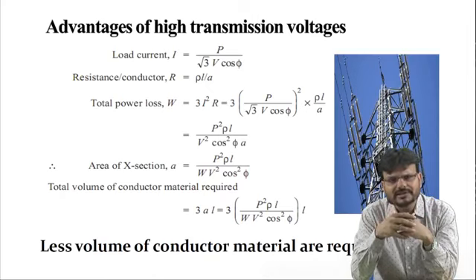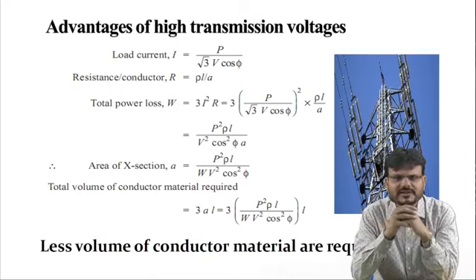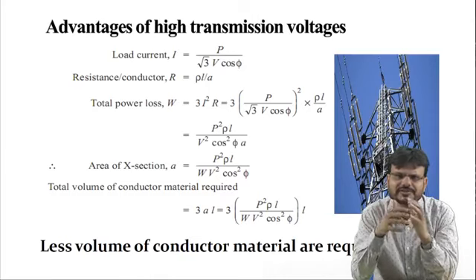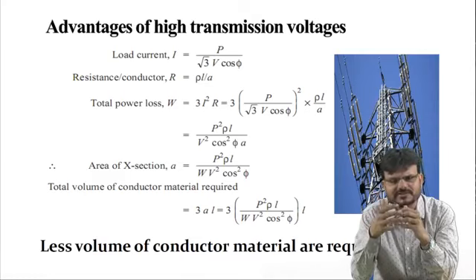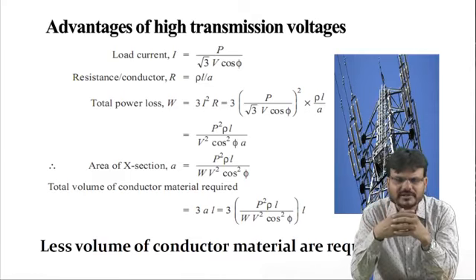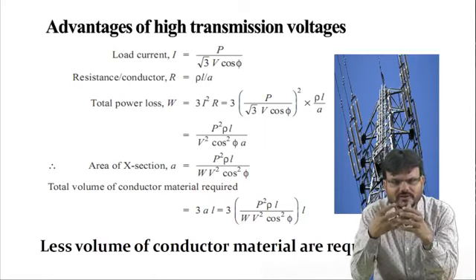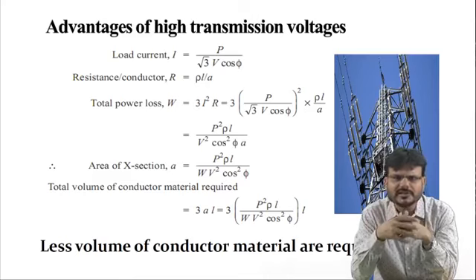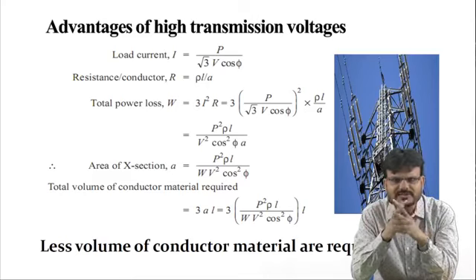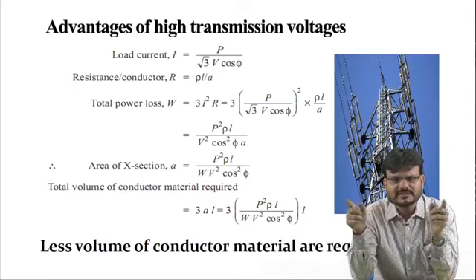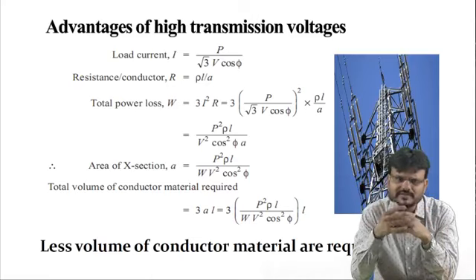So the total power loss W can be written as 3I square R. Just put the value I equal to P upon root 3 V cos phi, and R equal to rho L upon A. So what will you get? Total loss W is equal to P square rho L upon V square cos square phi A. Here you can see that the power is fixed, because every generating power station has a fixed generating capacity. This power plant may have a capacity of 110 megawatt or 220 megawatt or 440 megawatt, it depends. Suppose I am talking about 110 megawatt power generation. So this P is fixed, rho is fixed, the length of the transmission line is fixed, and for cos square phi I am assuming that power is transmitted at 0.8 power factor, and the area is also fixed.